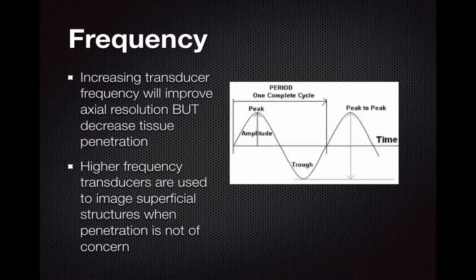Now to quickly review the frequency, like we said before, so the frequency is measured in hertz, which is cycles over seconds. So the more cycles you have in a given time, the higher the frequency is. Higher frequency in ultrasound is really good for high resolution images, but it doesn't penetrate well because you have high attenuation. And then the opposite is true for low frequency. If it's a low frequency transducer, you're getting this resolution that's not quite as good, but you can penetrate further into tissue because you have less attenuation.